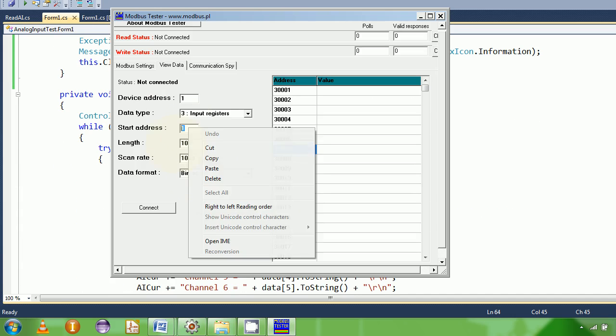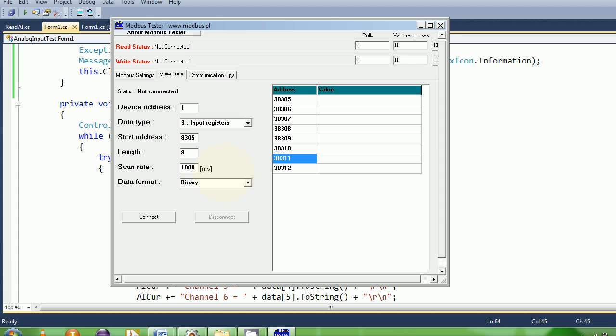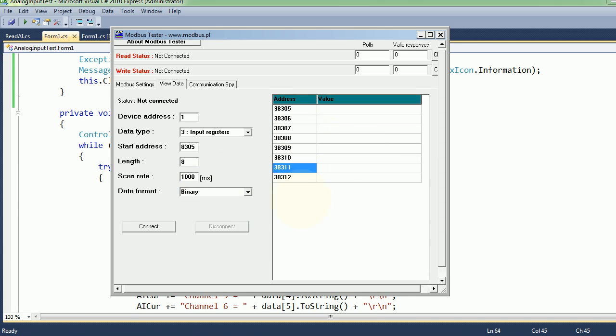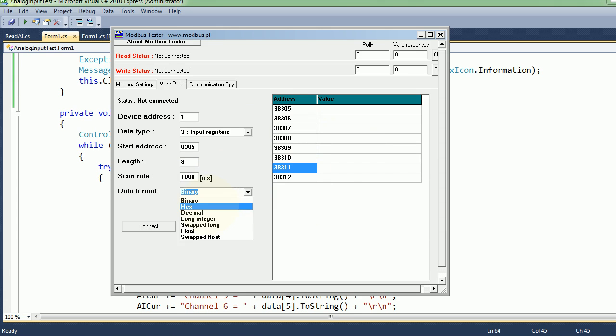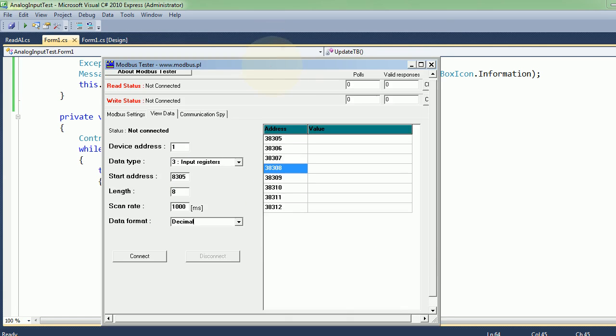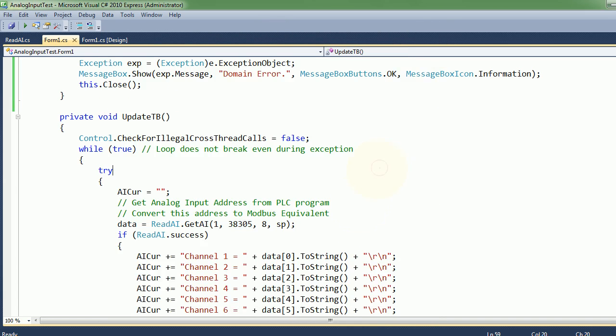You don't really need to enter the function code three - just paste the address here and it'll try to read all those values. For length - how many analog inputs do you want to read - for me it's eight. Scan time is one thousand milliseconds, which is one second. For data conversion: for coils you'd want binary, but for testing purposes decimal is also good. Long and float I've used a lot, but for our testing purpose it will be decimal.